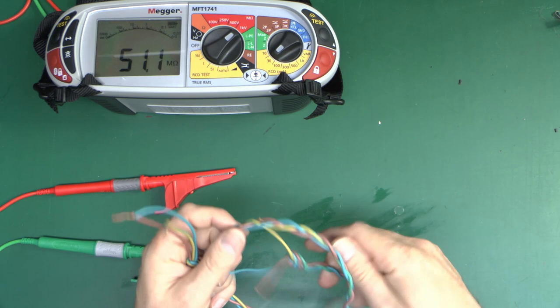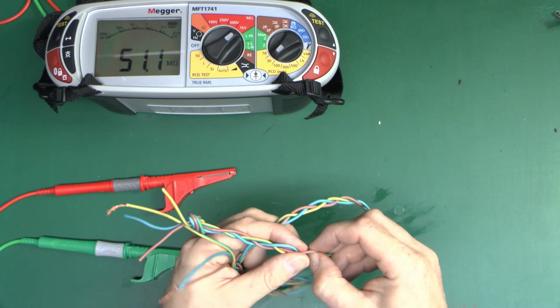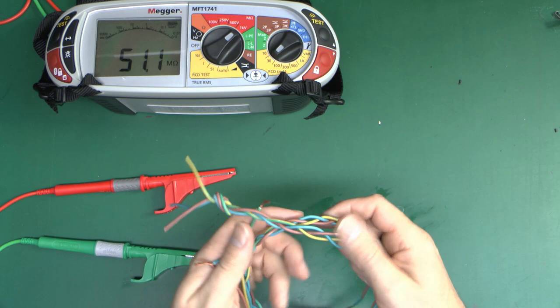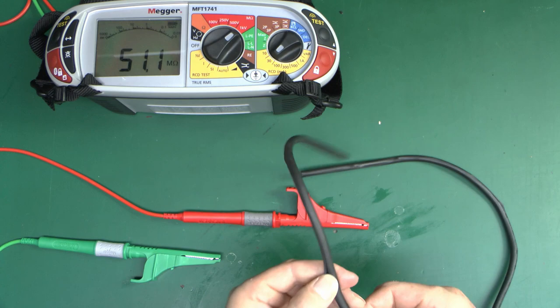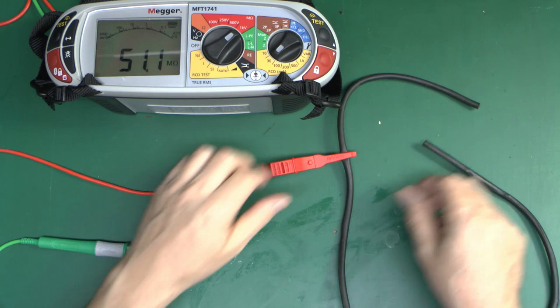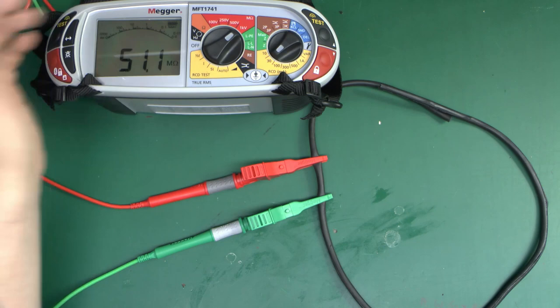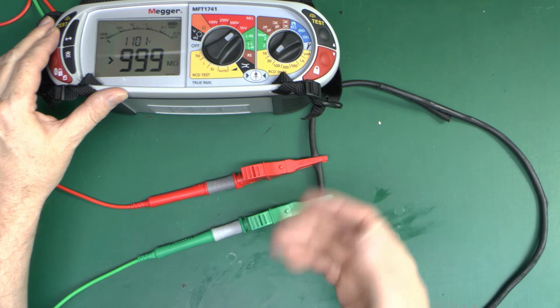And say this is not too clear, well it's some kind of rubbery material. If you sort of scratch it there it does sort of go to a lighter shade. So it is a rubber, or some kind of rubbery material. But obviously either say water's got into this and caused the insulation to be degraded, or it was degraded in the first place. So this has had adequate time to dry out. Now one last thing we could do is just to test the insulation itself. This is the black outer covering, which you should expect to be totally open, but let's shove it in the jaws here, put a moderately short piece between that. Going away, this is just supposed to be black rubber material that shouldn't have any conductivity at all. We'll use the 1000V just to see what gives. Yep, and as expected greater than 999 megohms, so nothing there. So it's definitely whatever's on the colored insulation here.